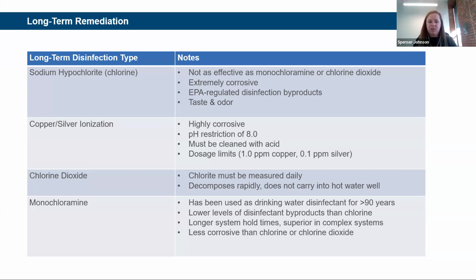And for silver, you have the limit of 0.1 ppm. With those limits, we've seen a lot of facilities where they're at those limits and they're still unfortunately getting positive results, so you don't have room to move with that. So we have seen a lot of facilities moving away from copper silver ionization.